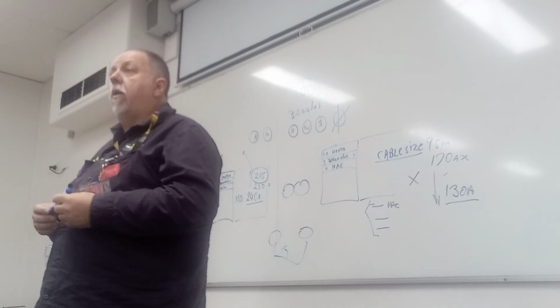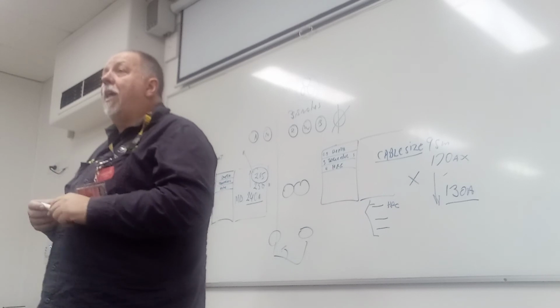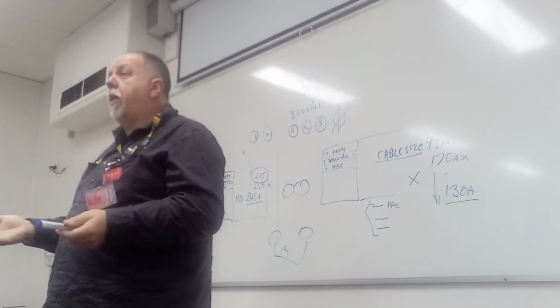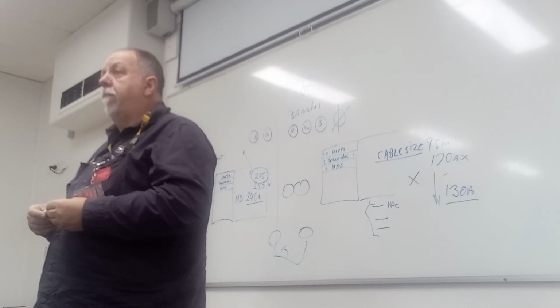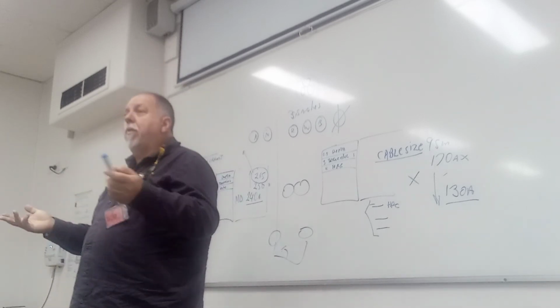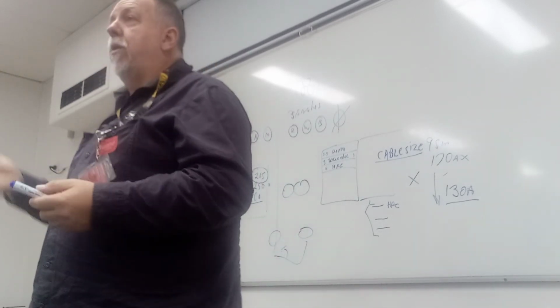So they don't realise that each cable is going to have 200 amps. That's exactly right. Yeah, right. You're not looking for 400 amps on one cable, you're looking for the size of each cable. So if it's 3 cables, it's divided by 3, same thing. That's the most common mistake. In the future, because... Sorry? They'll get sacked in the future because they've overquoted. No, you'd end up with a cable of like 150 square mil, and thinking, hang on a sec, what am I going to do with the other cable?